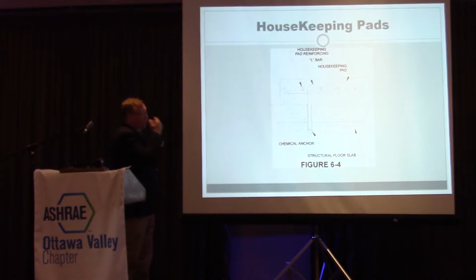But the US code keeps changing. They'll say if you hang a bunch of little pipes on a trapeze and it weighs more than 10 pounds a lineal foot, then you've got to brace that. That was in for 2 cycles, and the newest cycle got rid of it. The codes are like, whoever got enough votes this year didn't get enough votes next year, so stuff that was put in 4 years ago was out this year.